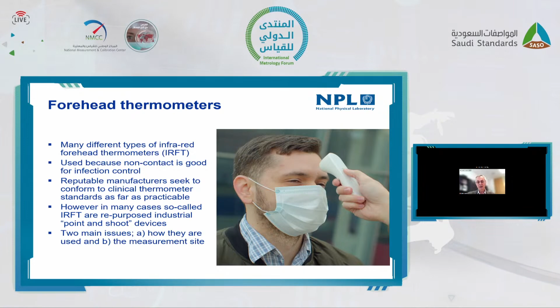So for instance, how they're used. You're really supposed to get very close to the forehead to get a small spot in the center of the forehead, as illustrated here. But sadly, people try to move further away, maybe to keep away from the patient. Unfortunately that means you capture some of the hair as well as the forehead, and the hair, certainly in the UK, is usually cooler. So you nearly always measure a low temperature with this type of device, missing fevers the person may have. Sometimes you measure even further away, and then you're actually measuring the wall or the environment behind, as well as the forehead and the hair. Who knows what temperature you are actually measuring if you're too far away. So it's really important to get the distance right when using forehead thermometers.